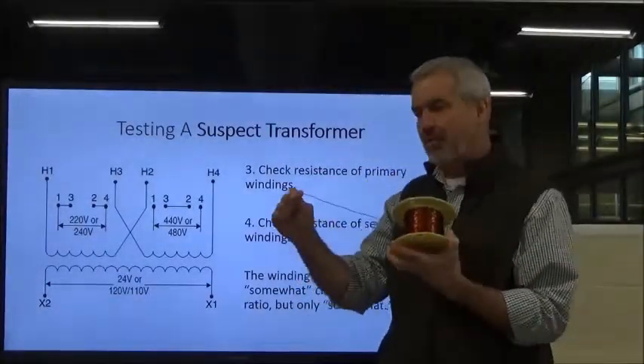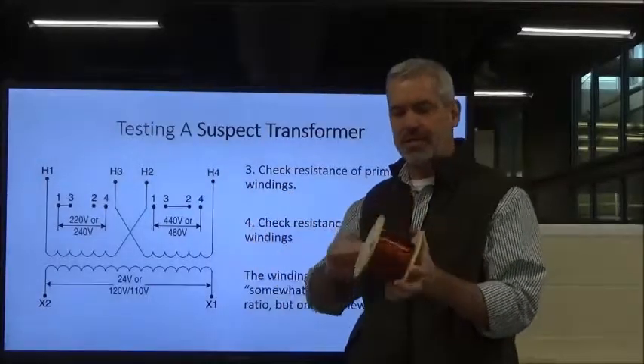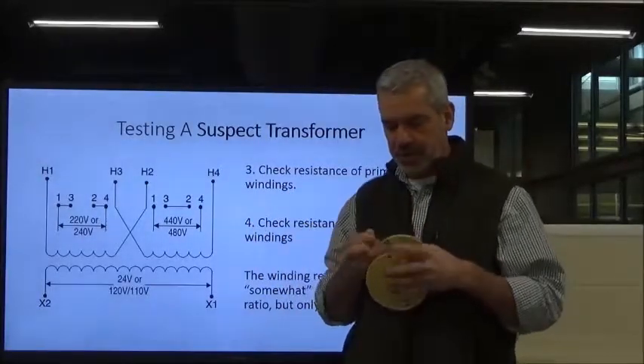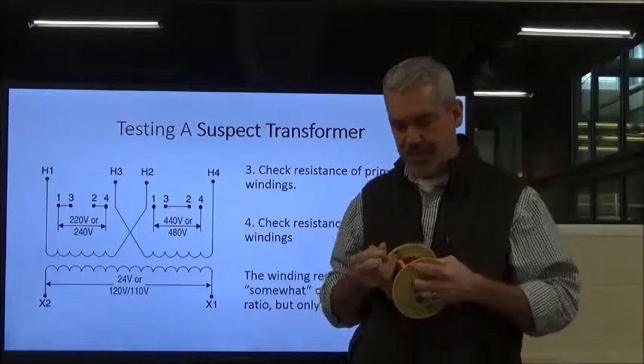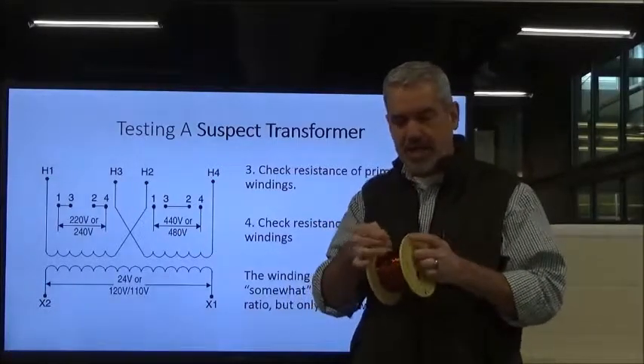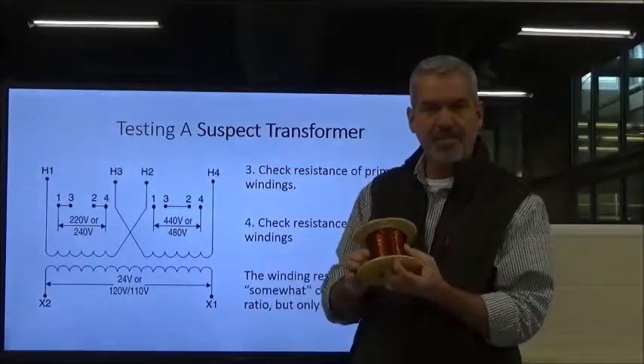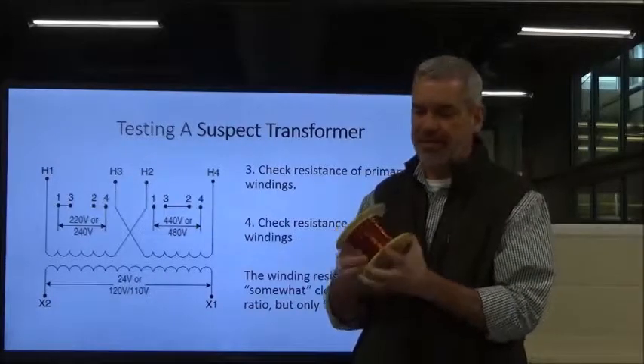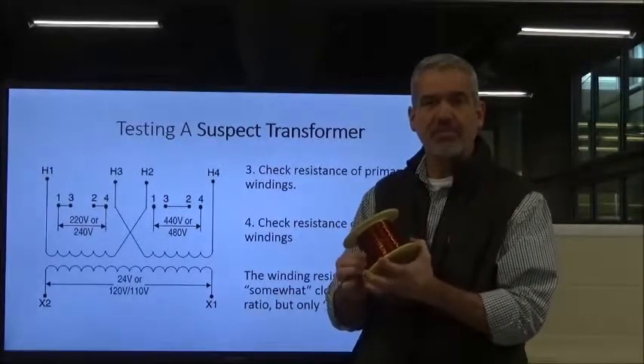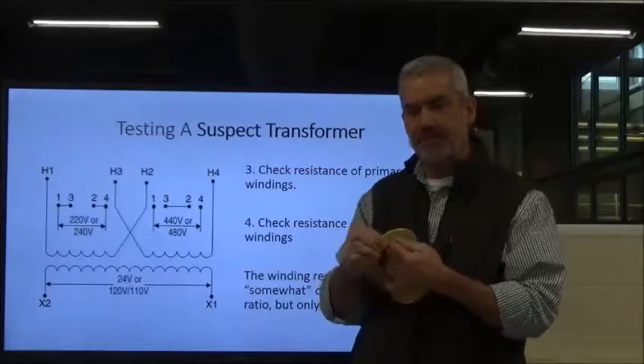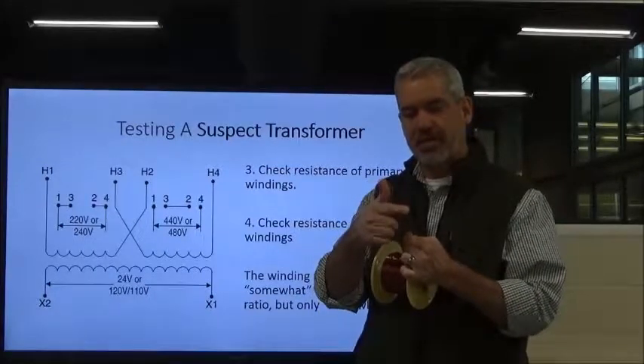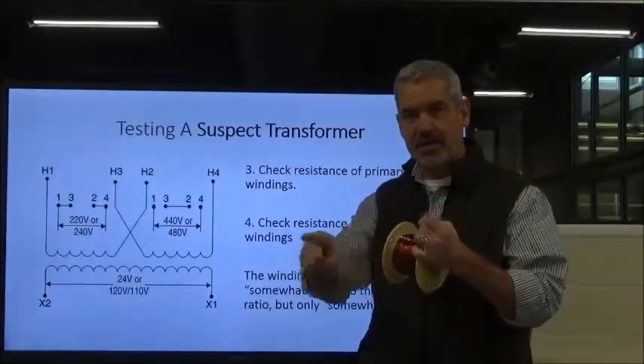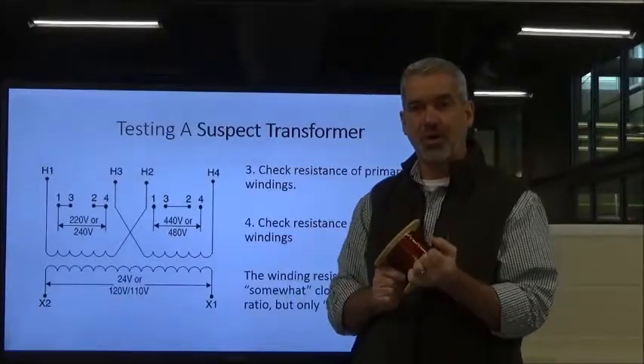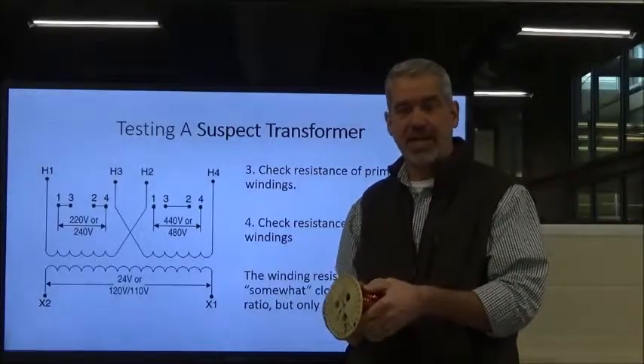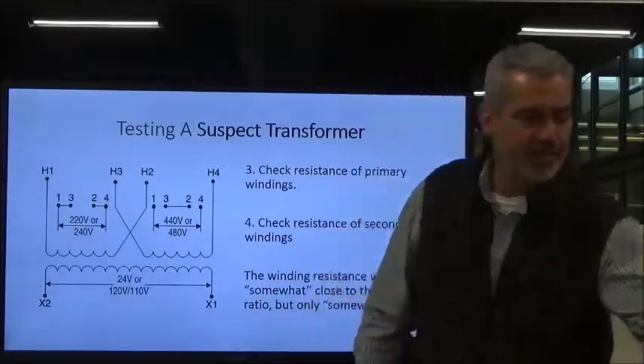Now, the coil of a transformer looks like bare copper wire, but it's actually transformer wire. It's a solid wire with a varnish or coating on it for insulation. These coils wrap around like this, and after a while there's a lot of vibration and heat, and it'll break that insulation down. Instead of the voltage going into the beginning of the wire and the coil and all the way out the other end, we'll wind up with a short, where it overlaps and makes contact. We don't want that to happen.